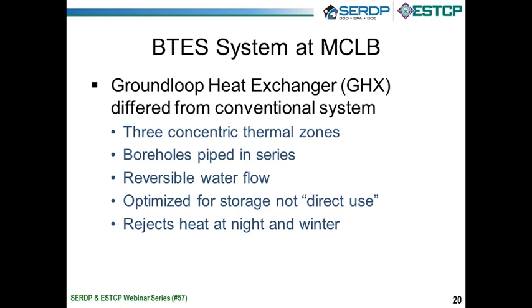And so our boreholes are piped in series. You get a little more pressure drop when you have to go through three boreholes in series versus them all being in parallel, but it does allow some thermal stratification opportunities. So BTES systems will usually have boreholes piped in series. The system in Calgary where they're storing heat has actually got six boreholes in series. We modeled that for Albany, but in the end, the pressure drop was too high and the modeling didn't show a big benefit. So the final design was a series of three boreholes.